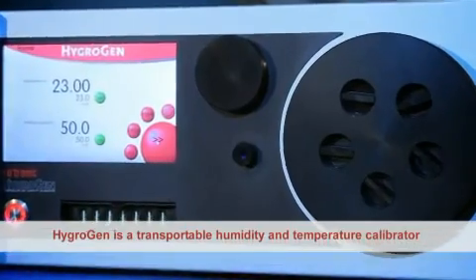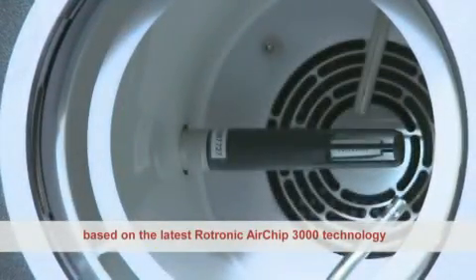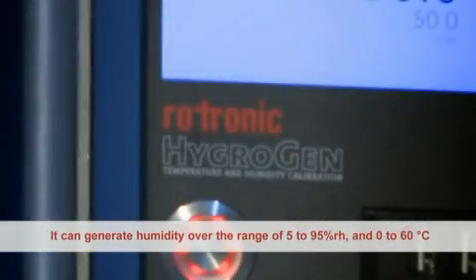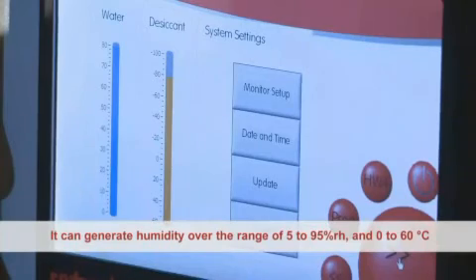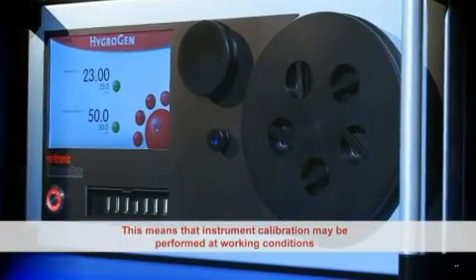HygroGen is a transportable humidity and temperature calibrator based on the latest Rotronic AirChip 3000 technology. It can generate humidity over the range of 5 to 95% RH and 0 to 60 degrees C temperature, meaning that instrument calibration may be performed at working conditions.